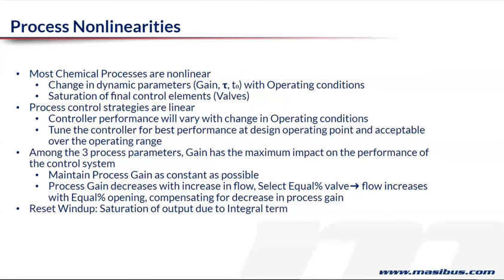Process gain decreases with increase in flow. We talked about the steam heater. As the flow of the medium increases, the process gain will decrease, and it is very easy to imagine why. As the process flow increases, you need more heat transfer to take place to keep the output temperature at the same point. And the moment you need more steam, that means your gain has decreased.